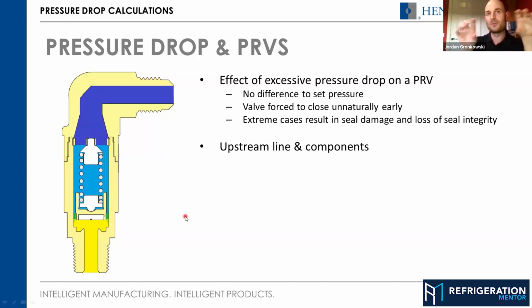If you have a pressure drop in that line because your pipe is too small in diameter or it's too long, you've got excessive pressure drop. This is effectively what the valve sees. So when it initially opens, everything's static, nothing's flowing. It'll open with that high pressure and it'll vent. But then as soon as it opens and the flow starts, that's where this build-up pressure drop starts, and the valve sees a lower pressure.